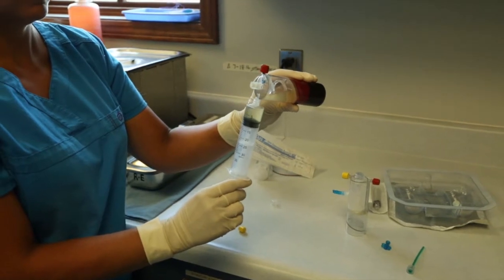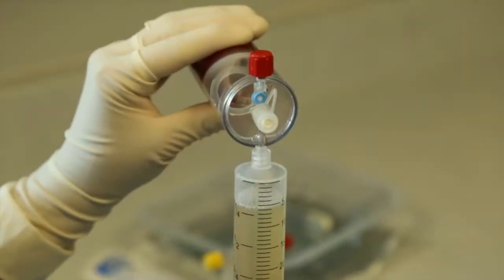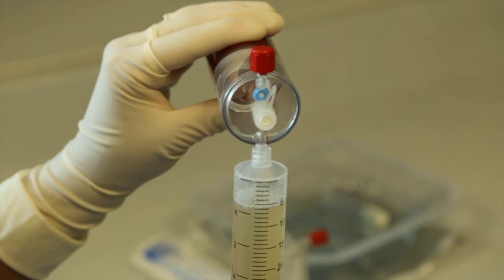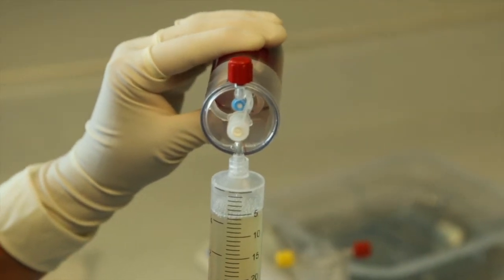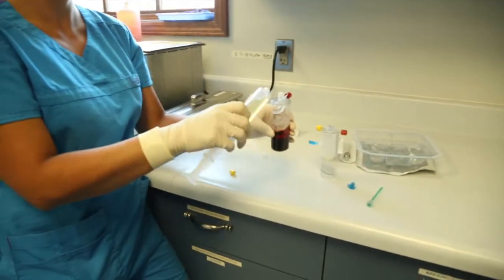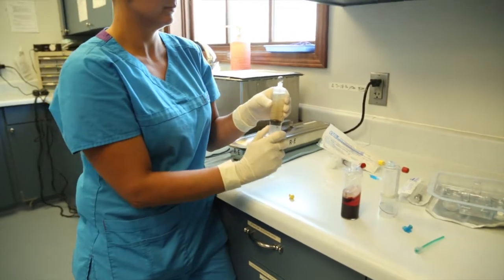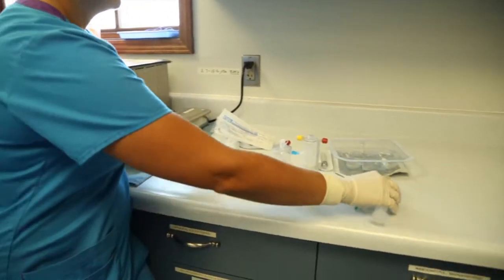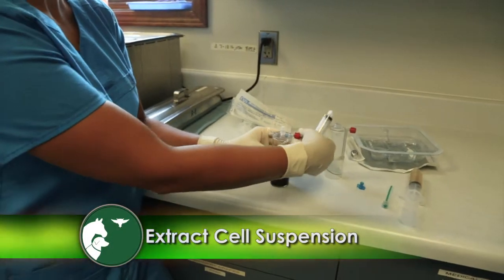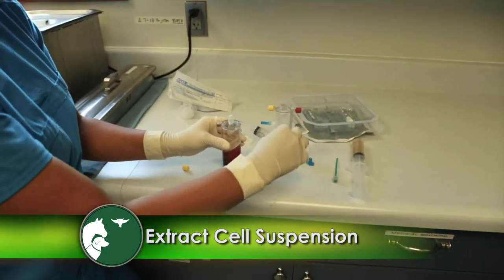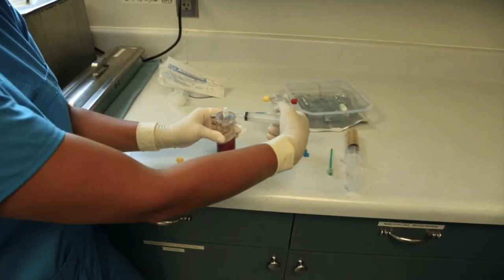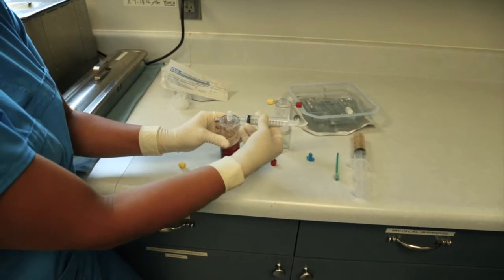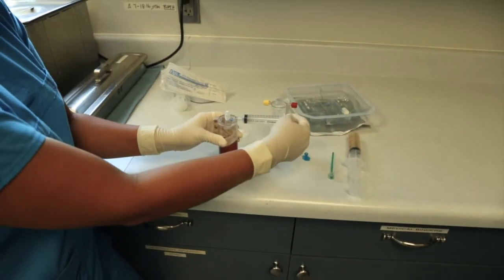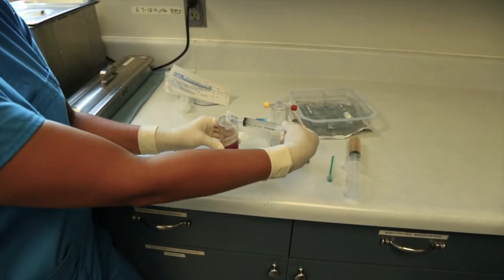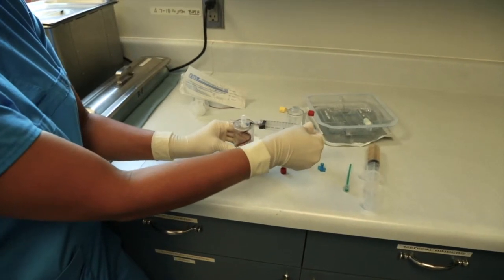When removing the platelet-poor plasma, tilt at an angle, but avoid inverting, keeping the fluid below the top blue vent. When complete, replace the yellow cap on the device. The platelet-poor plasma that has been removed can be discarded. To extract the platelet-rich cell suspension, remove the red cap, labeled number 3, and connect a 10 ml syringe. Secure the connection on the device using a luer lock syringe. It is less likely to loosen when shaking and resuspending the solution.